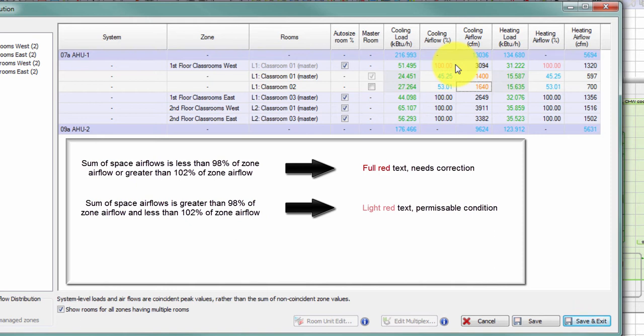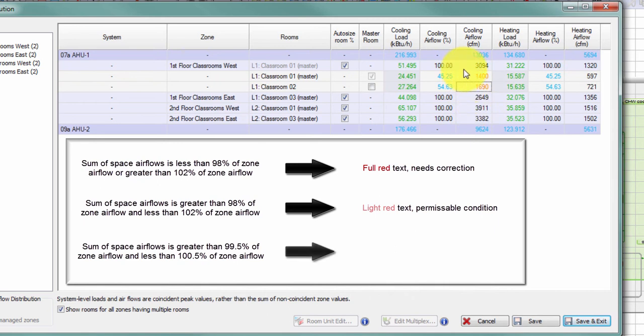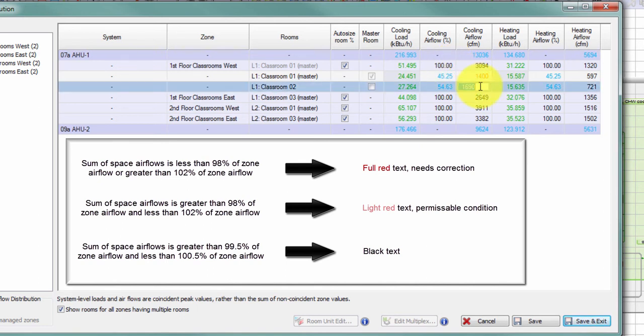Once within the 98%–102% range, I'm allowed to proceed — the light red is just a warning. When within plus or minus 0.5% of 100%, the software rounds to 100% and shows the text in black. To make the value exact, I'll change it to 1694.